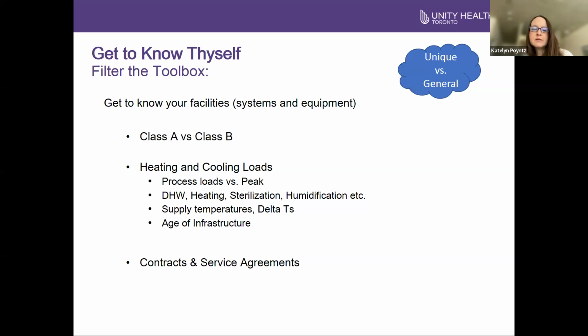Supply temperatures and delta T's - understanding your current set points and what they need to be. For example, we have a heat recovery chiller in one of our facilities, and a demand flow response system for our chilled water wasn't as beneficial because we were trying to hit a higher temperature or different delta T's across our equipment.